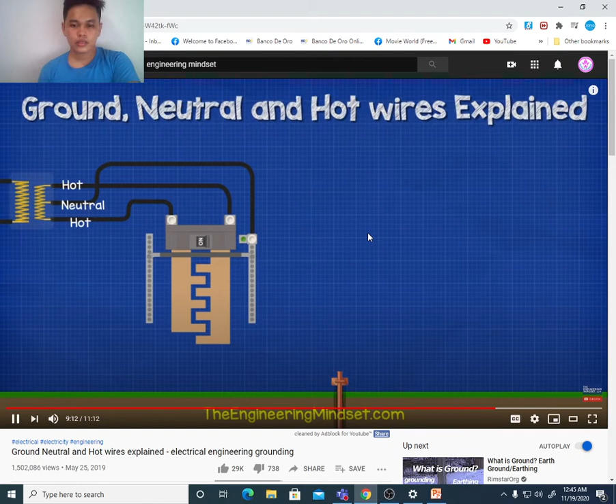Connected to the main panel, we will find a thick copper wire which leads out to a ground rod. The ground rod is buried into the ground outside near the property. This rod is not used for ground faults, its purpose is to dissipate static electricity and external surges. So yan, nagkakabit din ng ground rod. Ang purpose ng ground rod is i-dissipate yung static electricity from dito.